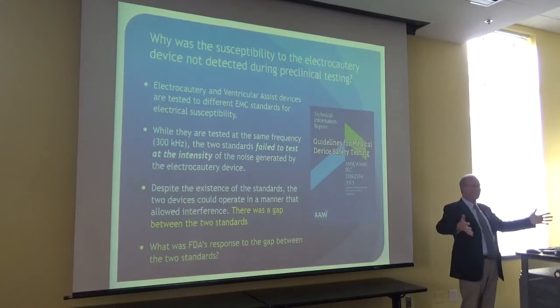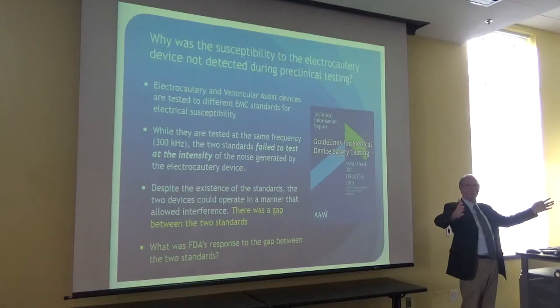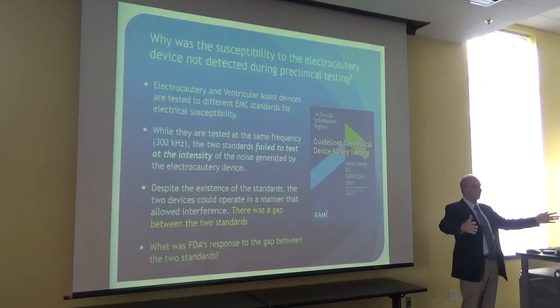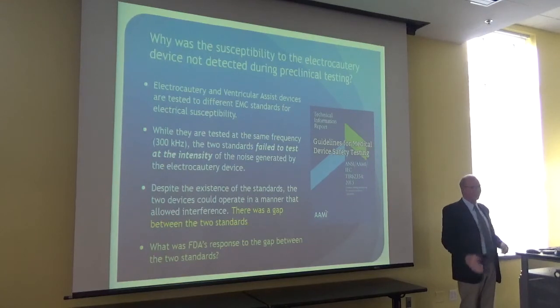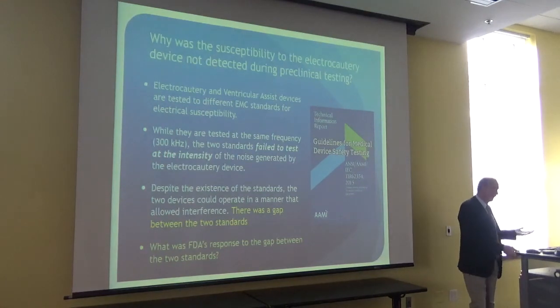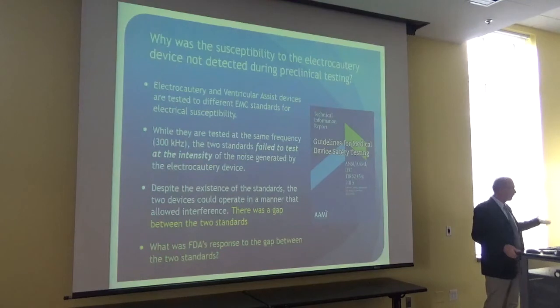So even though we tested and passed our electrical safety, we passed it enough for FDA, there was a gap in the standard. And so we went to FDA and FDA said, yeah, you passed your testing, and they passed their testing. It's great, but there's a problem in the field.